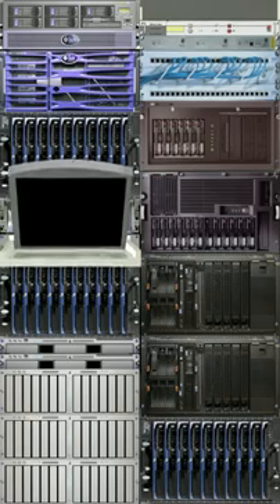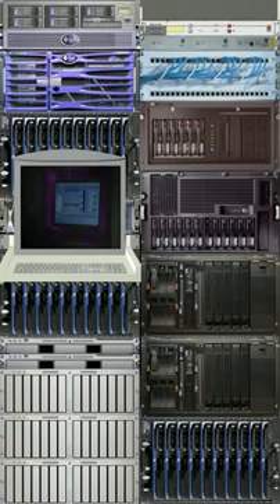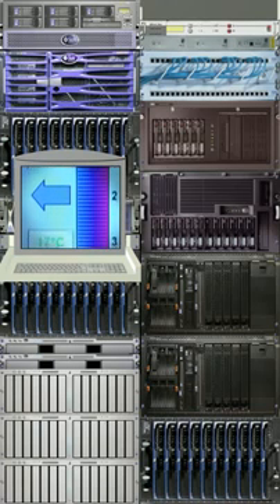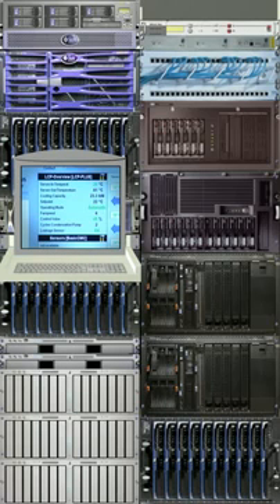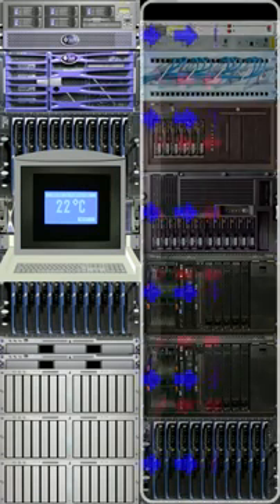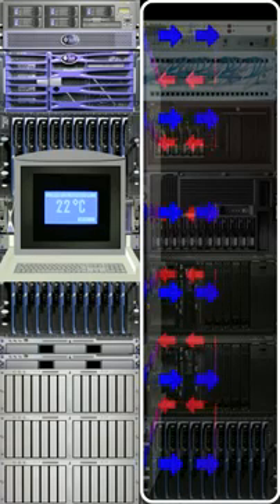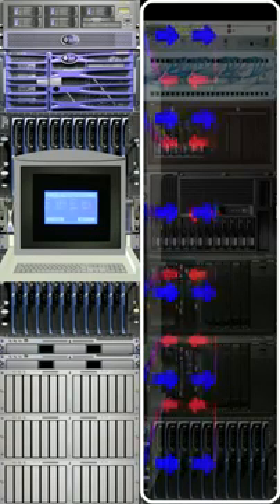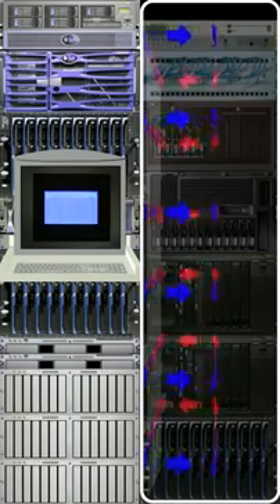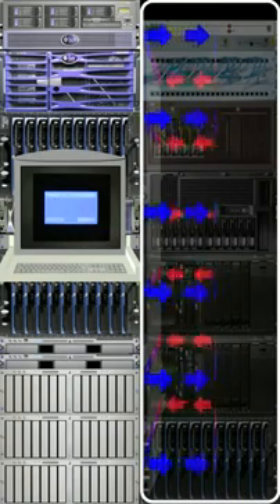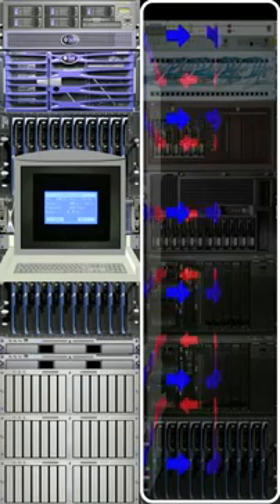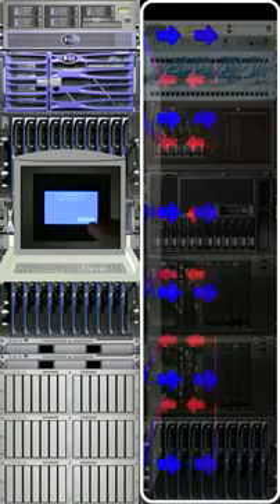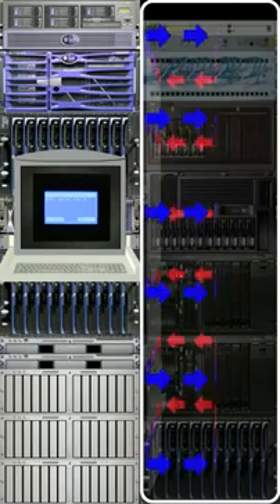Cooling is only one part of the functionality of the LCP Plus. Remote monitoring and control is essential so you understand what's going on within your high-density enclosure, and also you can adjust any parameters to suit individual applications. A backlit touchscreen LCD permanently displays the average server inlet air temperature so you get an immediate indication of cooling. This screen can be interrogated, so you can see fan rotational speeds, inlet and exhaust temperatures, water flow, inlet and outlet water temperatures, and of course, any alarm activity.